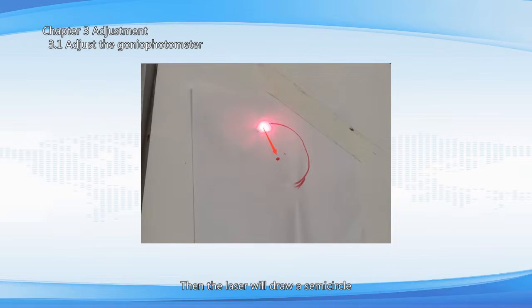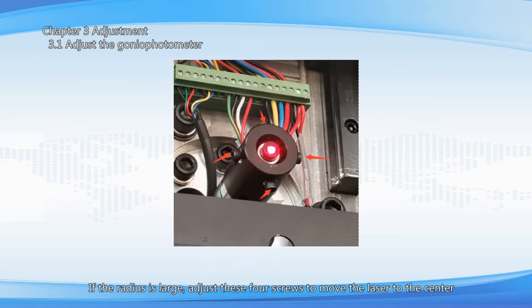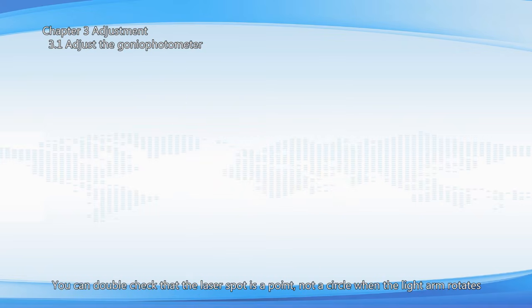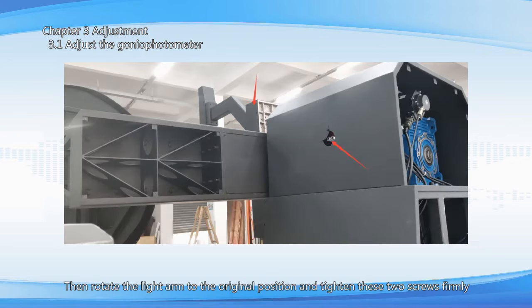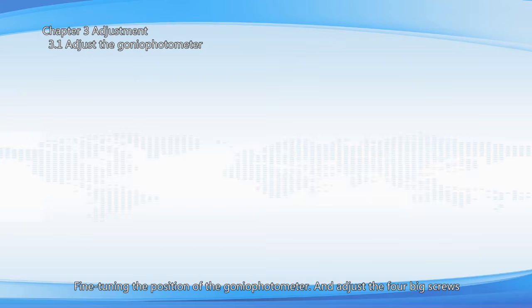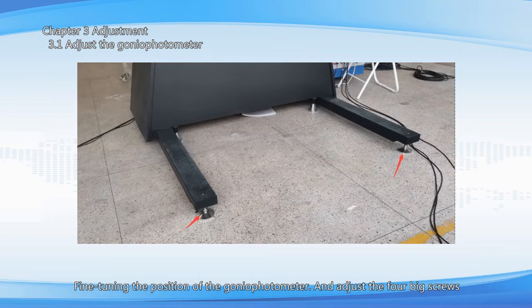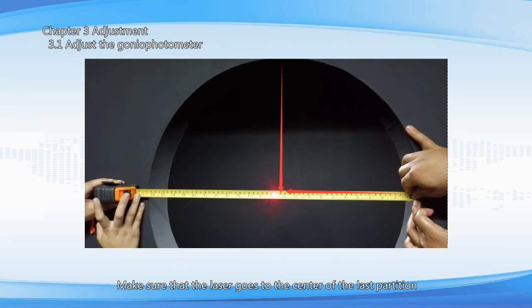Then the laser will draw a semicircle. If the radius is small, it can be ignored. If the radius is large, adjust these 4 screws to move the laser to the center. You can double check that the laser spot is a point, not a circle, when the light arm rotates. Then rotate the light arm to the original position and tighten these 2 screws firmly. Fine-tuning the position of the goniophotometer, and adjust the 4 big screws. Make sure that the laser goes to the center of the last partition.